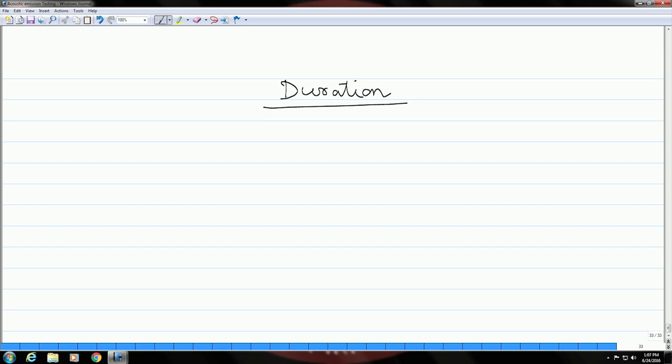There are different methods to filter noise, but you need to use a particular parameter which is closely related to the quality of the signal. The parameter duration is closely related to signal quality, meaning the duration of acoustic emission signals coming out from different sources will be different. This parameter can be used to identify the noise.